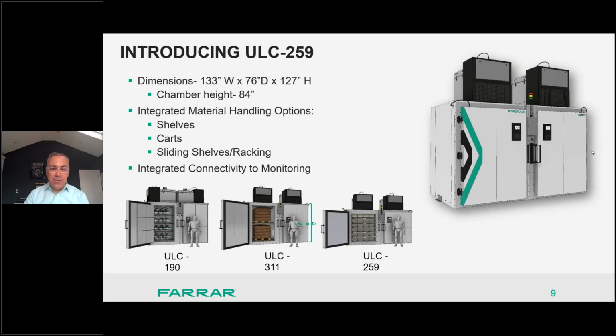But finally, with the release of the 259, we've added integrated connectivity via Modbus to export all of the points measured in our freezer to your monitoring solution, whether it's a building management system, an automation system, or just a custom monitoring solution from any temperature monitoring company you might be using. Our protocol should be easy to integrate and allows you to really dig in and predict any issues that might come up before you have a temperature alarm.